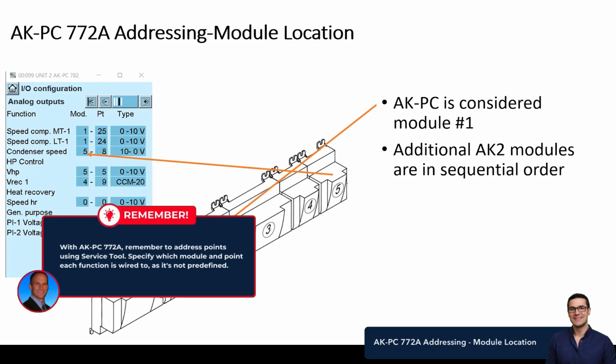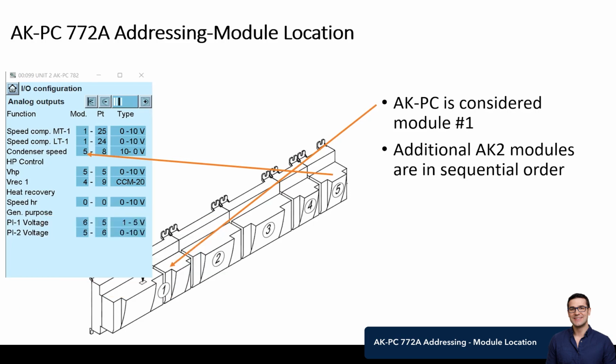So as far as your pressure transducers, your valves, we've got to define where that controller should be driving that signal to those devices or reading the feedback from them for a pressure or temperature. So part of your service tool setup will be to get in and address the points. It's not a predefined position where everything would be wired to. So you can see here the screen from service tool.